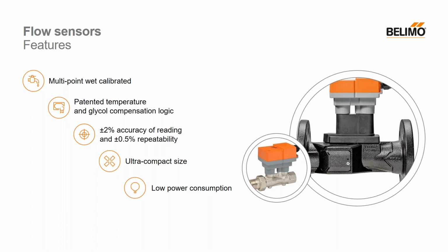We developed something called glycol compensation. So as the viscosity of the liquid changes due to the amount of glycol that's in the system, the meter knows to compensate to keep the accuracy of the flow reading very high, which is generally going to be plus or minus 2% of accuracy with a plus or minus 0.5% of repeatability. They don't take a lot of power. They're relatively small, and these are inline flow meters.